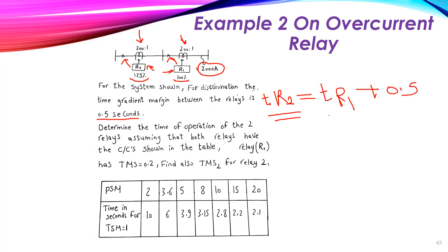From here you will understand the discrimination between the two relays — how can you discriminate between different relays. This relay operates this circuit breaker, and this relay operates this circuit breaker. For the discrimination, the time gradient margin between the relays is 0.5 seconds. This means that the time of R2 will be equal to the time of R1 plus 0.5 seconds, so R2 will operate after R1 by 0.5 seconds.